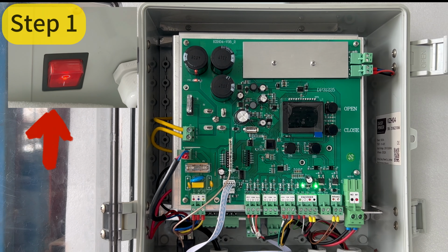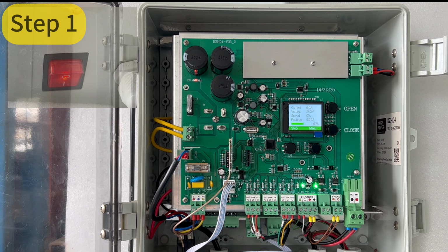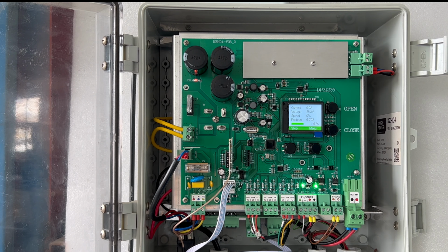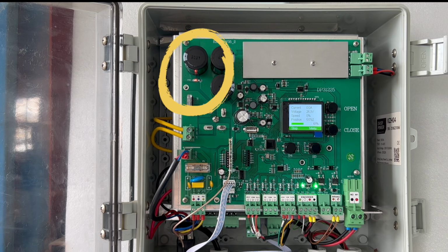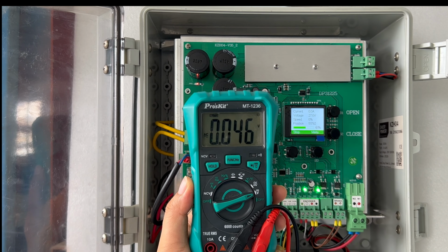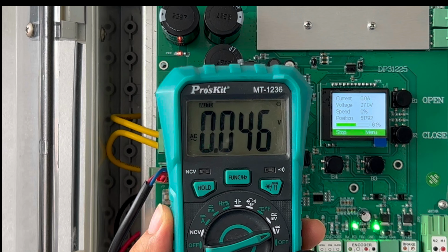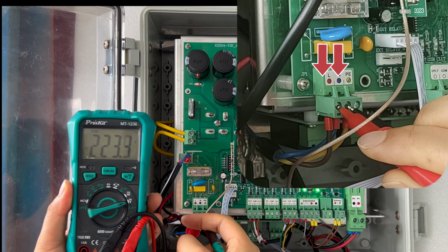Step 1. Power on the control box. Even if your box is not working and the screen not lit up, still you need to power it on. If you see this red light, it means the mainboard is powered up. Dial the multimeter to AC voltage checking. Here is the power supply for the control box. The voltage is around 230 volts.